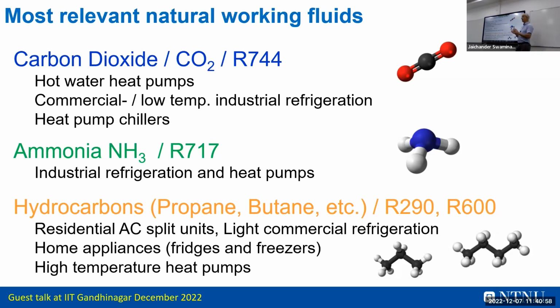It depends very much on what kind of duties you want from the system and at which time of year. If you have a combined mode, like for heat pump chillers in a hotel, that means you always have a cooling demand and always a heating demand for water. Of course you do this by storing, so if it's a bit delayed it's no problem. Then you get a really high COP.